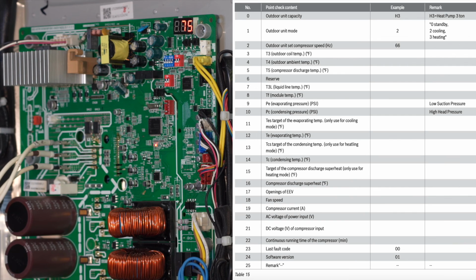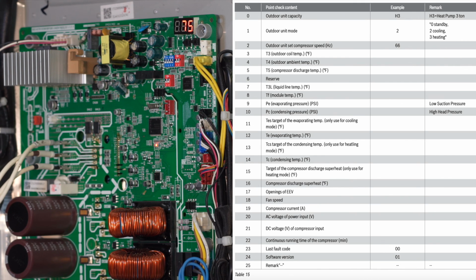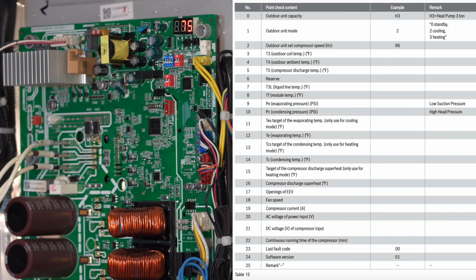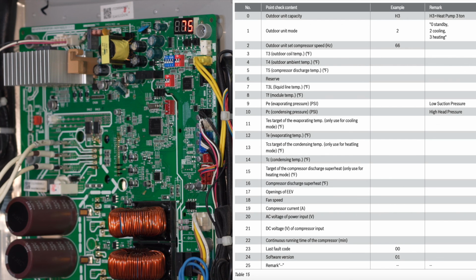If I was in the heating mode, that number is going to be all over the place, modulating, load matching what's going on, and that's when we get to use the E valve in its fully operating condition where it's modulating. Yes. There's nothing on the board for you to be scared of. There's voltage, AC, DC, but we saw a while ago how to check the board out, how to verify that we don't have any more stagnant voltage there to be a problem.